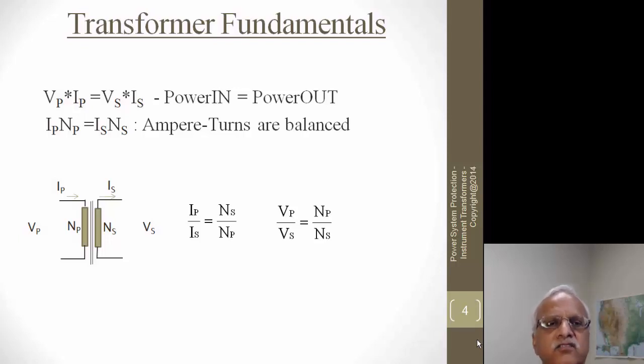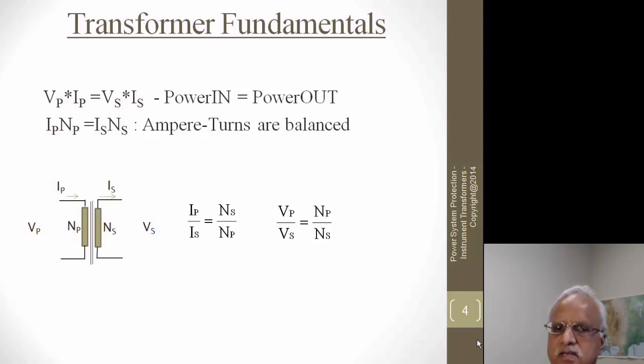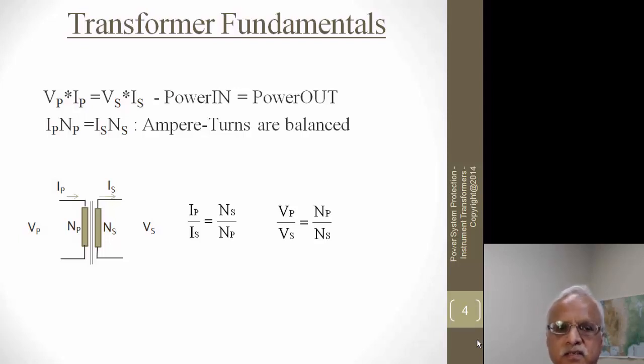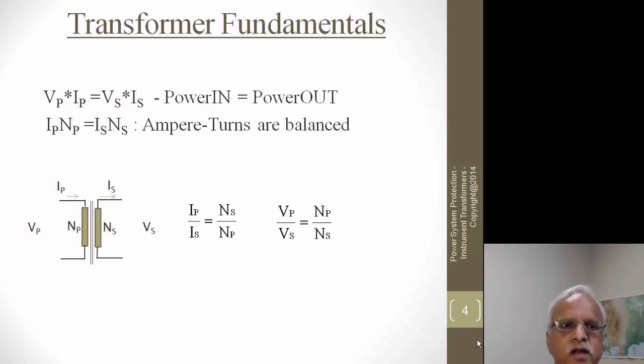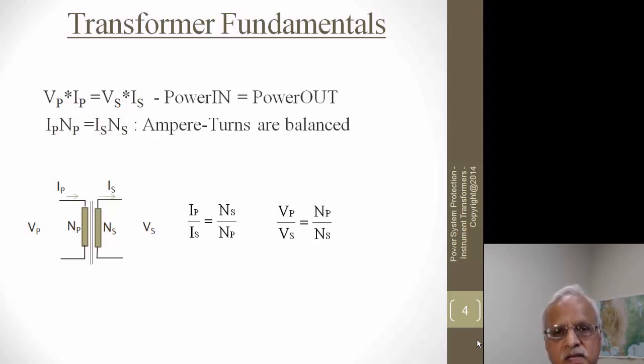Before getting into current transformers, let's look at transformer fundamentals. Whether it is a voltage or current transformer, the power into the primary winding equals the power out: VP times IP must equal VS times IS, where P is the primary winding and S is the secondary winding. The ampere turns must also be balanced: IP times NP must equal IS times NS.